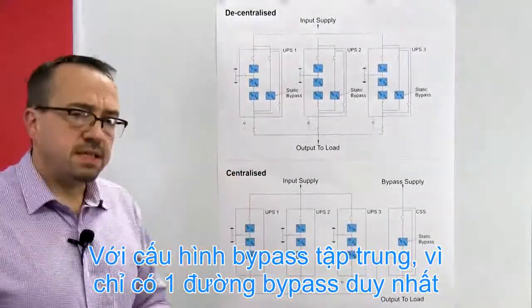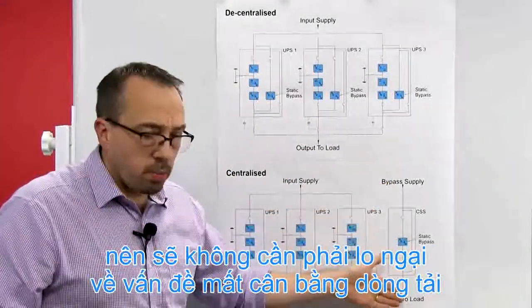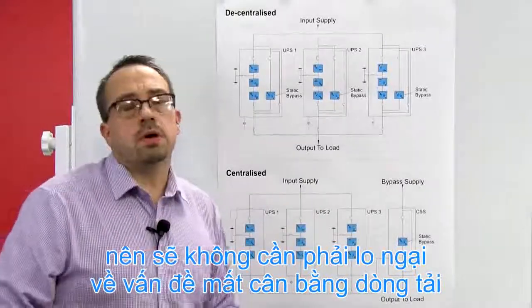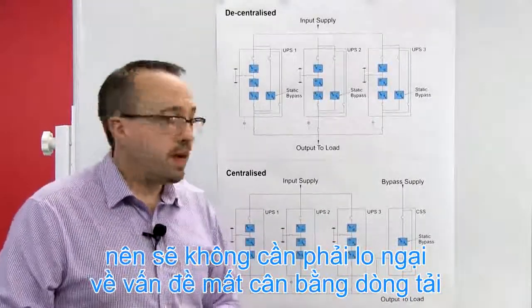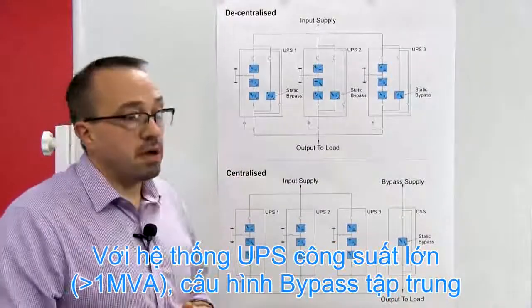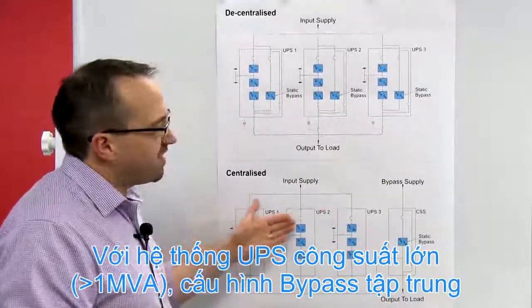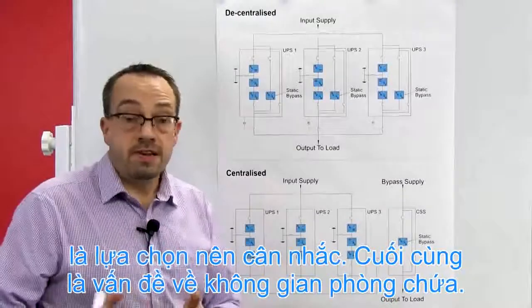Whereas with a centralized system, because you've only got that single bypass line, you've no longer got any power balancing issues, and hence, for many large installations, the centralized with a single bypass line is the preferred choice.